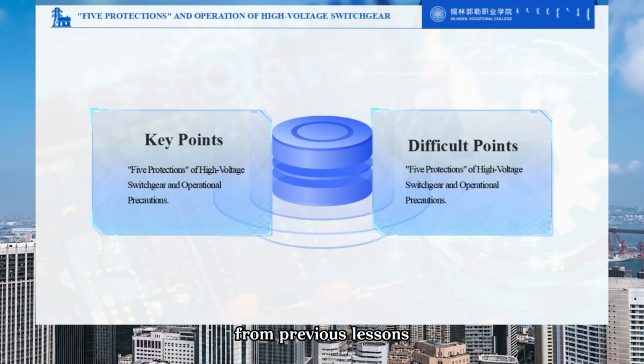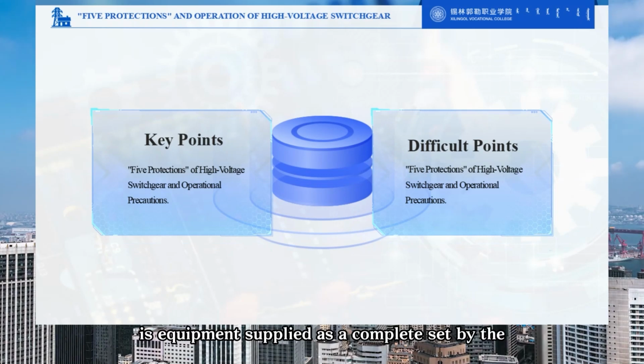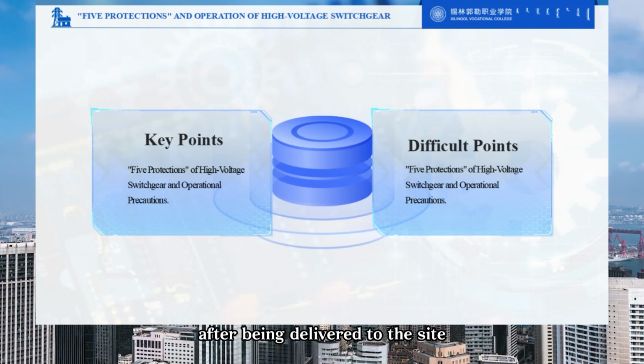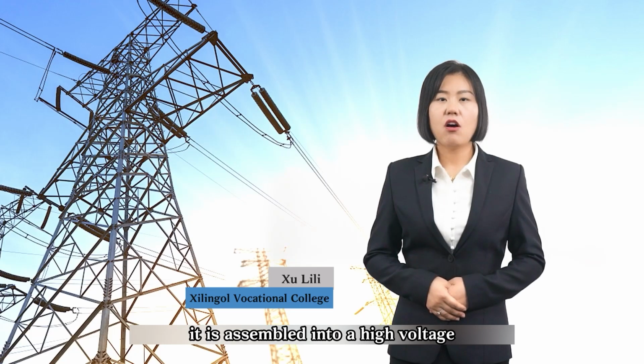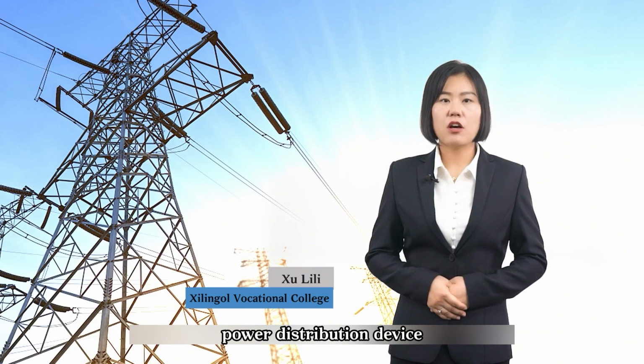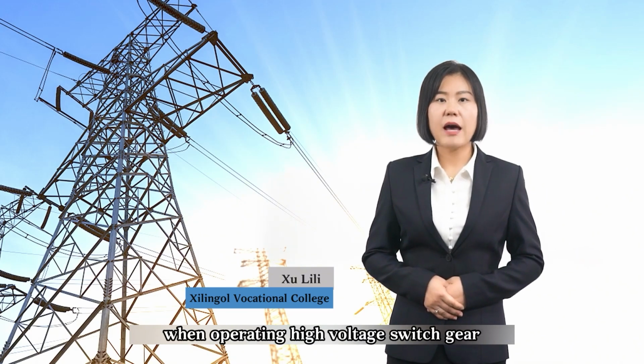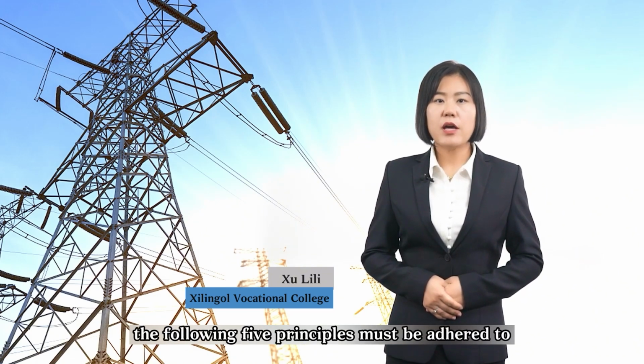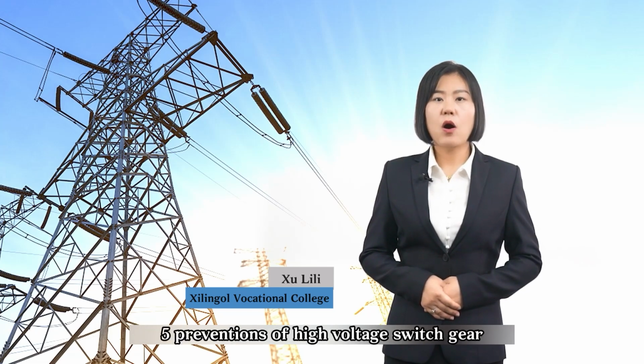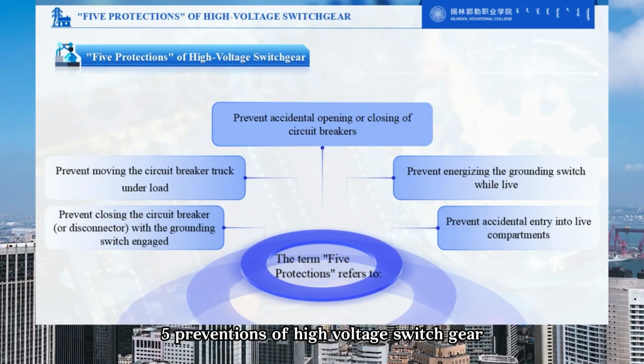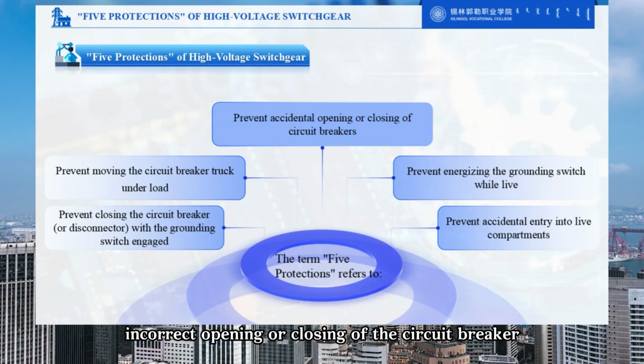procedures. From previous lessons, we have learned that high voltage switchgear is equipment supplied as a complete set by the manufacturer. After being delivered to the site, it is assembled into a high-voltage power distribution device. When operating high-voltage switchgear, the following 5 principles must be adhered to, abbreviated as the 5 preventions of high-voltage switchgear. They mainly include the following: preventing incorrect opening or closing of the circuit breaker.